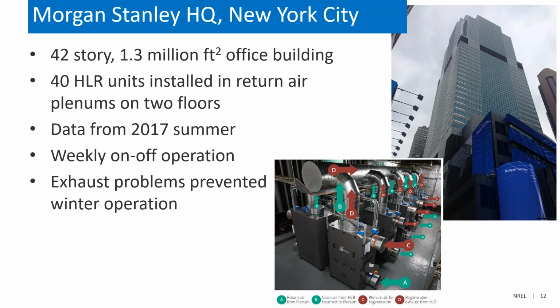This one, they were able to put the HLRs in the return air plenums. So there's 40 units in this building, 20 on the 7th floor and 20 on the 28th floor. And then we were able to collect performance data during the 2017 summer. Unfortunately, we were unable to monitor this during the winter time to get heating season operation because there were some exhaust challenges. Those have since been corrected, but we did not get winter time operation for the 2017-2018 winter.